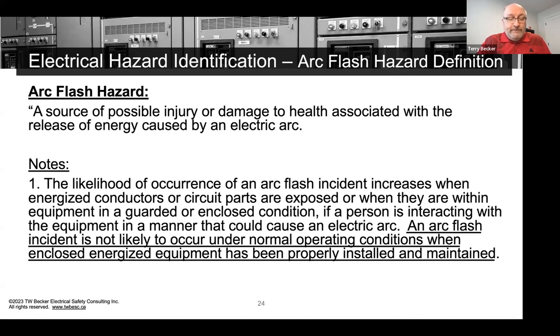Another myth in industry is that an arc flash is going to be 100% likelihood and we just can't go in front of electrical equipment even to operate it. That's completely wrong. And your company, in my opinion, does a risk assessment and controls that narrative to the worker. It's quite important because arc flash over the years has taken on its own personality, as I said, and there's lots of myths and misinformation that aren't substantiated. So control the narrative, substantiate using risk assessment for the equipment that you work on, right? To operate it, we don't need arc flash and shock PPE. When we open it up and go in, that's different. Work task dependent in that case.